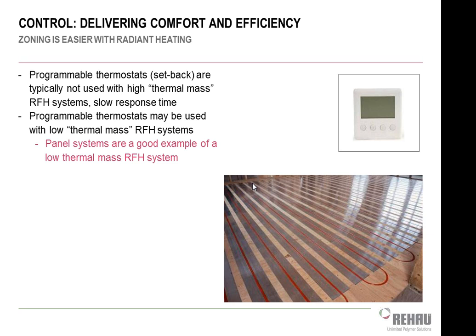Because remember, the thermostat is sensing air temperature, not really floor temperature. Although there are some fancy stats out there that can get a floor sensor and try to bias that, but those generally don't work out as well as you might expect. So the regular thermostat only senses air temperature. It can't react at the slow speed of this floor. So it ends up taking too long to cool down and wasting energy, and ends up taking too long to heat up in the morning, which causes comfort dissatisfaction from the occupants. So with the radiant floor system, the recommendation would be a non-programmable thermostat.